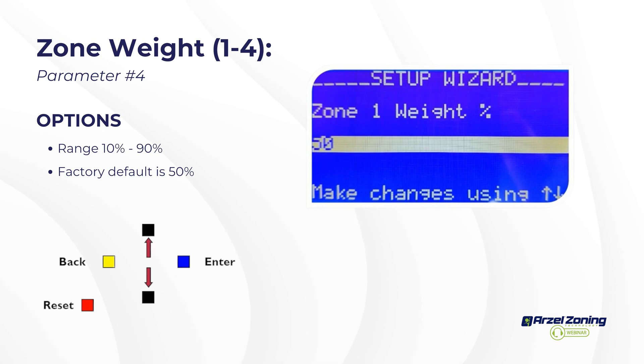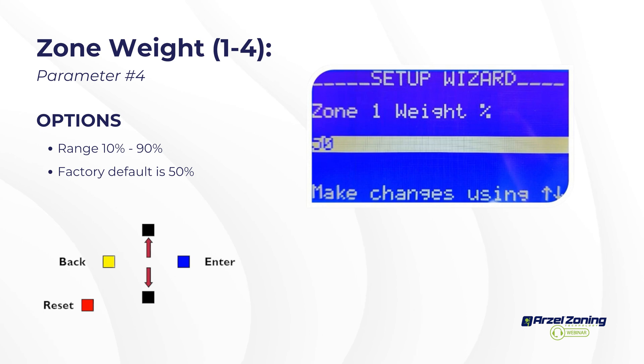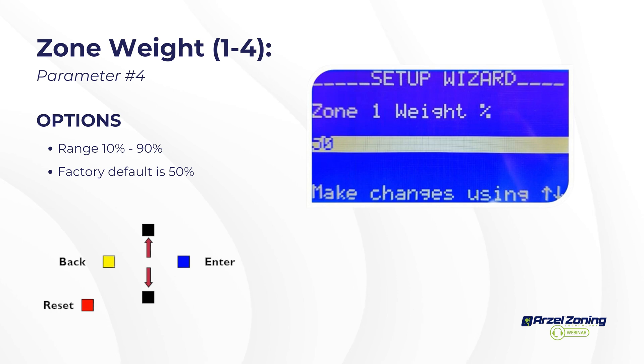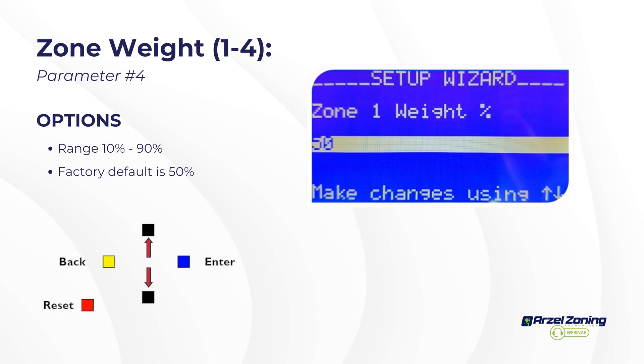In a four-zone system: zone one is large, leave it at 50%; zone two is medium, set it to 40%; zones three and four are small, set them to 20%. Zone two (40) plus zone three or four (20) equals 60, which is greater than 50 — W2/Y2 allowed. But zones three and four alone (20+20=40) is less than 50 — W2/Y2 disabled, requiring a third zone to call.